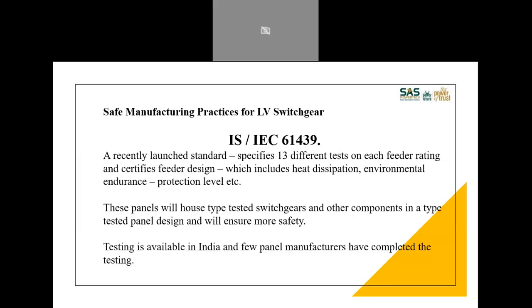Suppose I have a type tested breaker, and if I keep side clearance less than what is recommended, then that type tested breaker also can fail because of flashovers. So this design ensures all that. And 61439 has a lot of provisions. It makes the panel manufacturer study the site conditions first. There are a lot of forms available in this standard. So he has to take down what is the humidity, whether there is any corrosive atmosphere at the site. All that he has to tabulate and then design the panel.